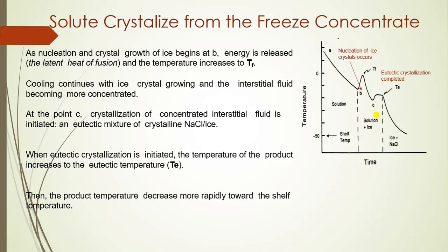A eutectic mixture is a mixture of two crystalline substances that melt as a single pure compound. When eutectic crystallization is initiated, the temperature increases to the eutectic temperature TE, and then the product temperature decreases more rapidly towards the shelf temperature because there is no remaining liquid substance to absorb heat and solidify. Once the eutectic temperature is attained, the temperature reduces towards the shelf temperature, as seen in the diagram.